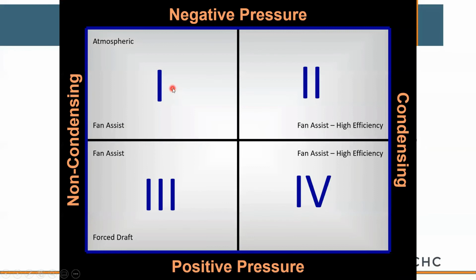There are different vent categories. Your gas barbecue on your back deck, your atmospheric boiler, was category 1. Typically it uses galvanized flue products. Anything else tends to be a special vent material. Condensing boilers, categories 2 and 4, tend to require either some grades of plastic or stainless steel, as well as category 3, which is kind of a sidewall vent application, or maybe a forced draft application.